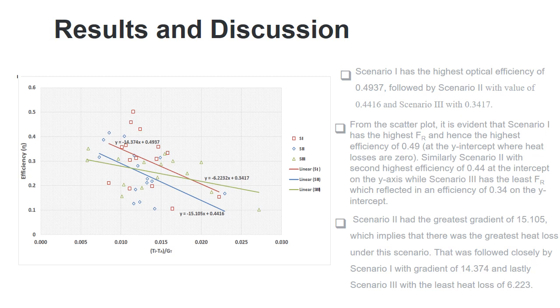scenario 1 did not practically record the highest heat loss. This could imply that the heat loss is not only a function of wind speed. However, scenario 3, which had the lowest wind speed during the test, recorded the least heat loss as well. The value of UL varies with wind speed.